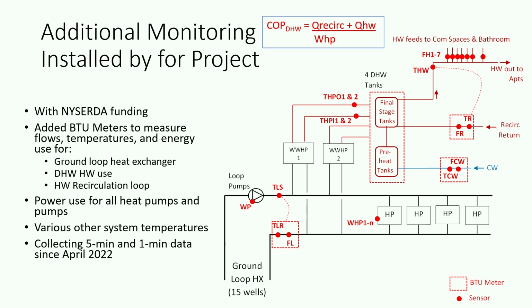Actually, can I borrow your pointer? Okay, so when we came into the building, there was already monitoring of the power use on every single heat pump. You can see there was a ground loop, and then the ground loop has various heat exchangers. We added a BTU meter to measure flow and temperatures so we could know the heat rejection and extraction from the loop. And what's novel about this system is there are water-to-water heat pumps that use the ground loop to provide water heating. And that's these units right here. We measured the power use of those.